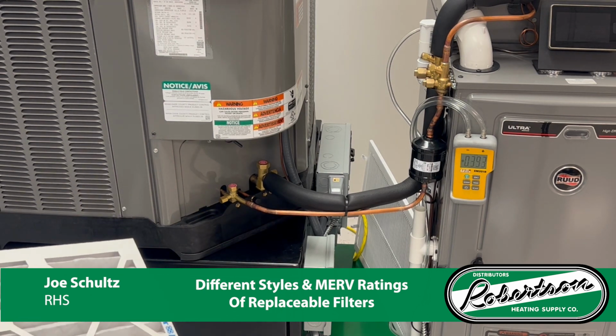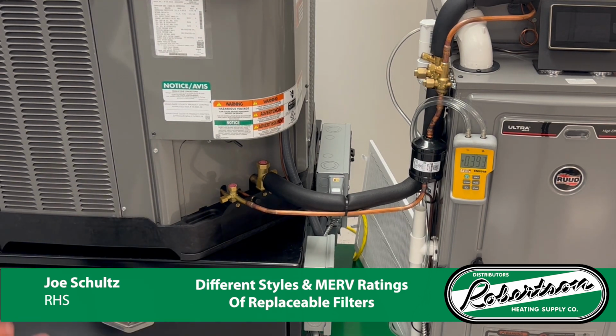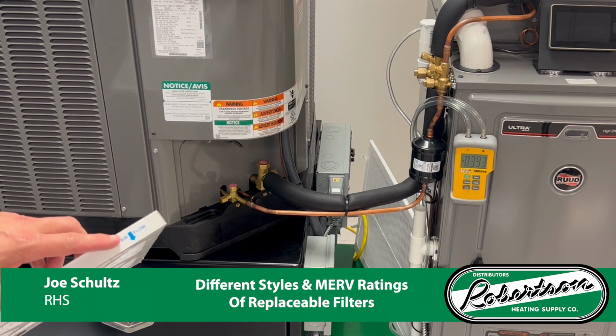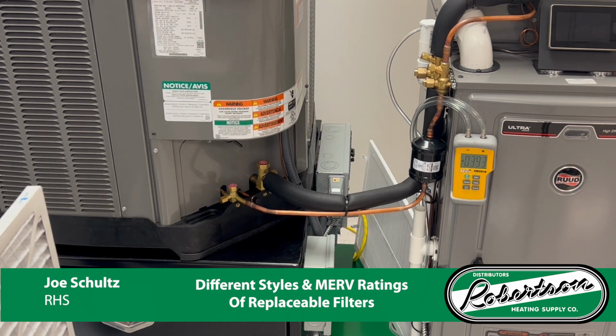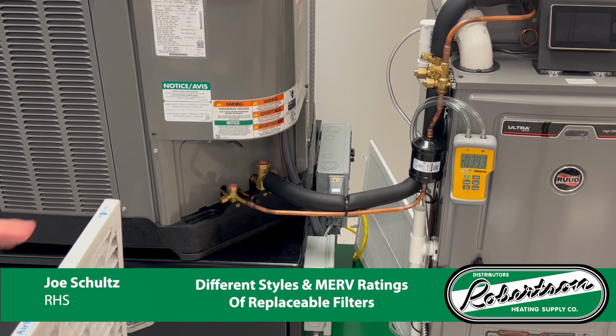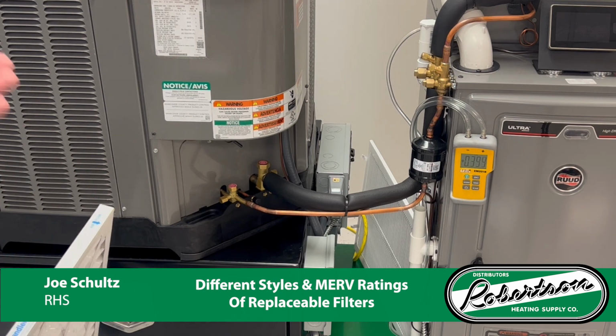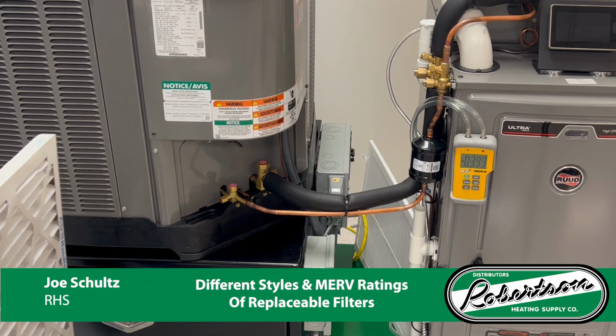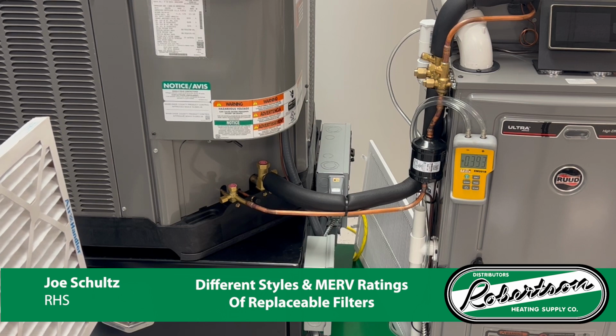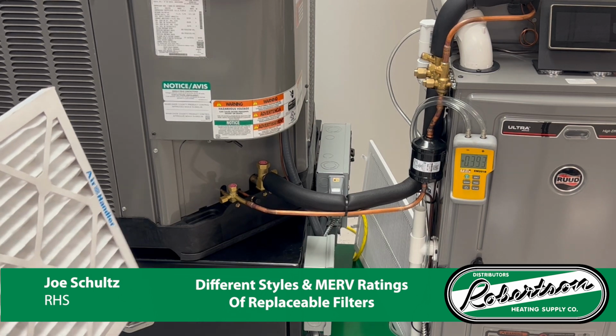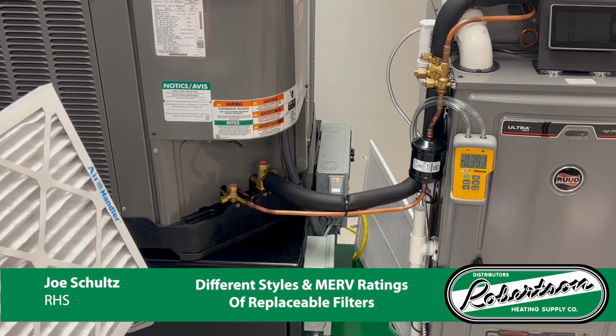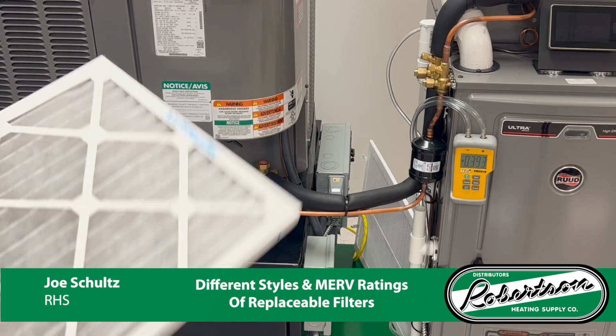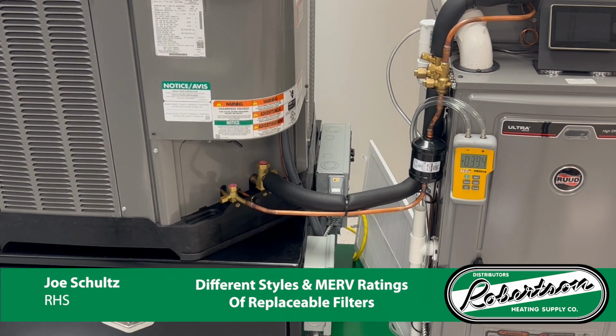So that's very important. Also, there's usually an airflow indicator on the filter, like this. And it's important, if you check it, to put the filter back in with that arrow pointing in the right direction. If you flip it around, you could release the dust particles off of the filter that you attracted to the one side of the filter, and then release them back into the furnace. So it looks like our static has moved up to 0.39 for this filter.